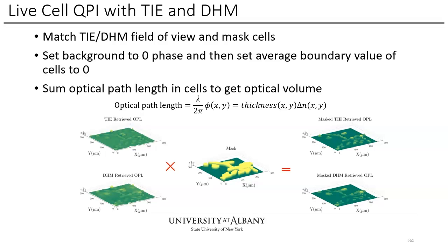We're not assuming anything. We're assuming that both of these could vary, and we're going to measure optical path length. Yes, N could vary. It doesn't vary too much, but it could. So what we get out may not be exactly proportional to thickness. It will be relatively close, but it will entangle thickness with refractive index.